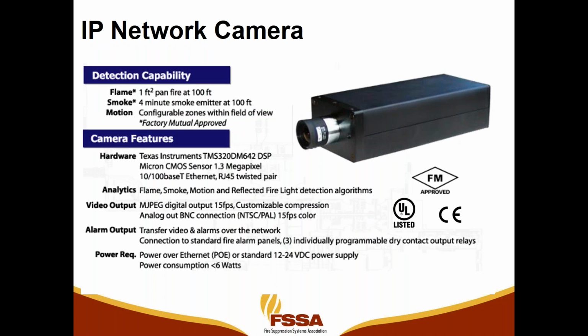So an example of a listed camera: the UL and FM standards require a 1 foot candle, 1 square foot pan fire of heptane detected at 100 feet, and a 4-minute smoke emitter detected at 100 feet. The detector is powered by 24 volts DC. There are alarm contacts on the back. For this camera, there are 3 alarm contacts.